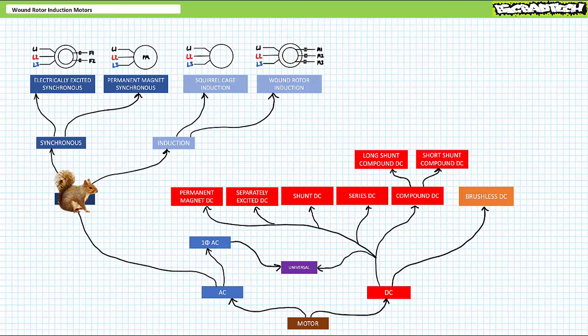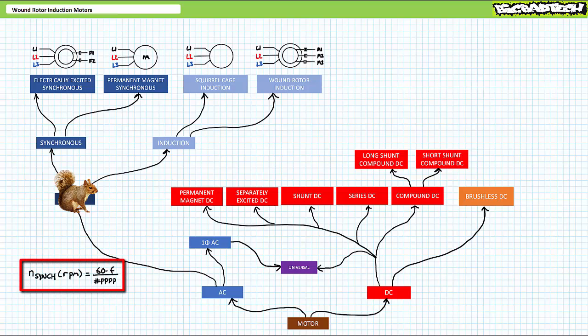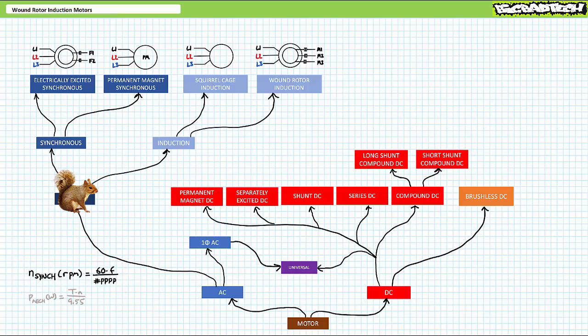Before we do so, let's pause at the split between the three-phase AC induction motors and three-phase AC synchronous motors and discuss some commonalities for these two important styles. Both synchronous and induction three-phase AC motors are characterized by a rotating magnetic field on the stator. The speed of the rotating stator magnetic field is known as the synchronous speed and is directly proportional to the excitation frequency and inversely proportional to the number of pole pairs per phase. Additionally, the direction of the rotating stator magnetic field can be reversed simply by interchanging any two stator leads inside a three-phase AC system. Lastly, one can determine rotating mechanical power in units of watts as a product of torque in newton meters times rotational speed in units of RPM divided by the constant 9.55. These properties remain true for all three-phase AC motors, synchronous and induction.